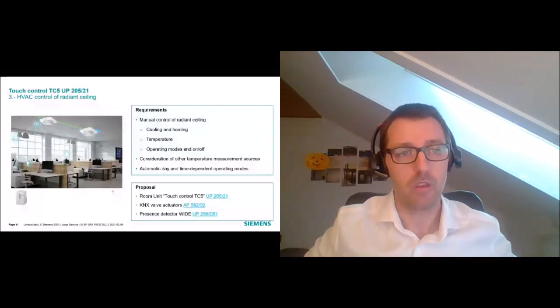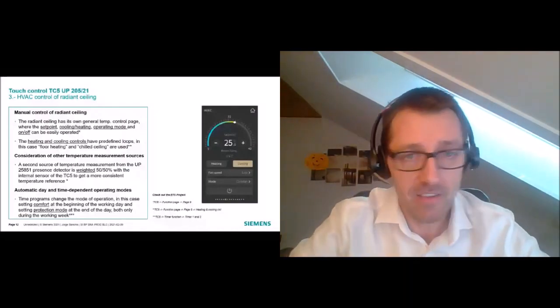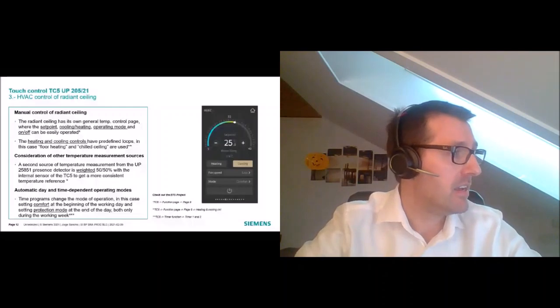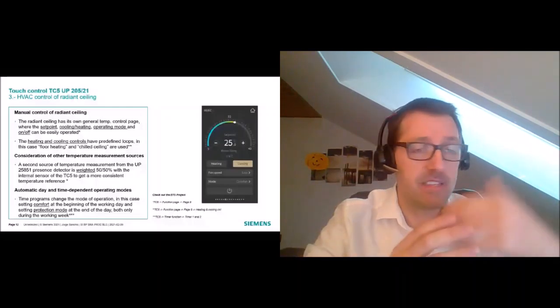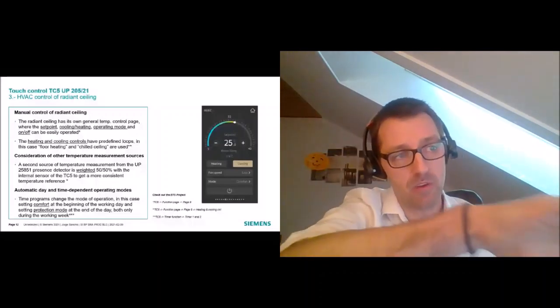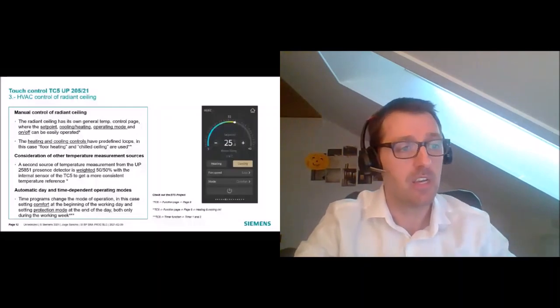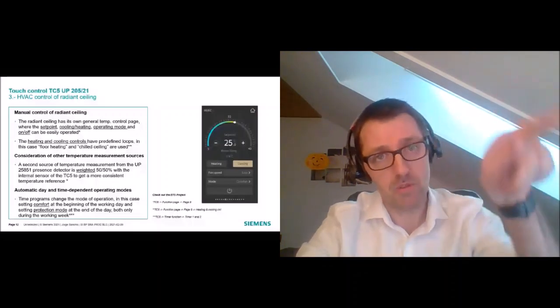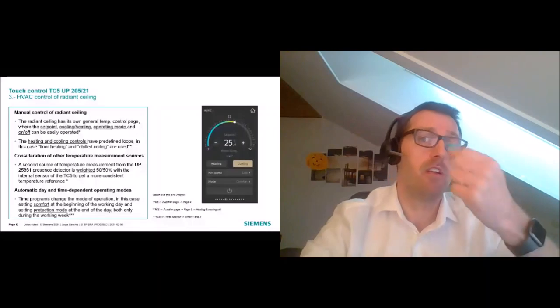For the first requirement — radiant ceiling, floor heating, or radiator — we configure the thermostat in the TC5. We go to the general temperature control page and enable the controls we want: setpoint, cooling, heating, operating mode, and on/off. Automatically, the TC5 generates a page you can see on the right — this is for the end customer with all the controls we enabled in ETS. The HMI is very user friendly, very easy to change the setpoint with a finger and switch between controls.